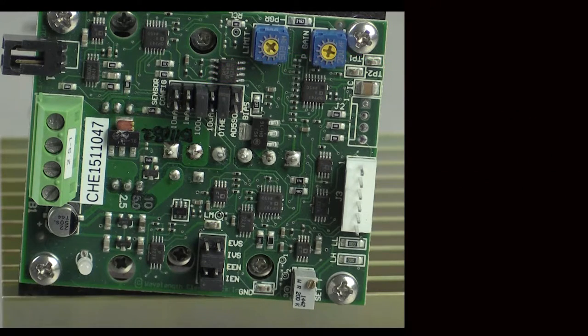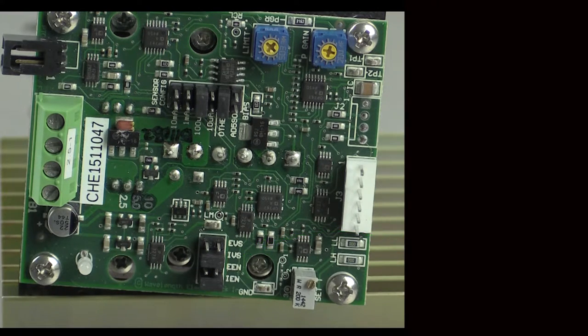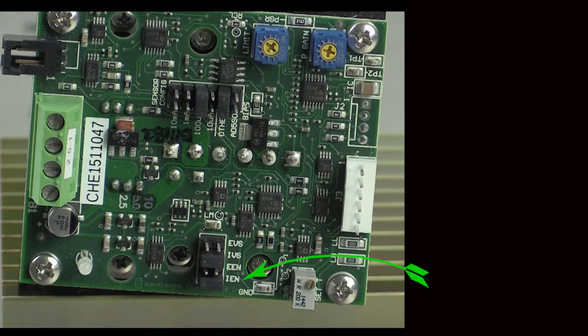We want to use the onboard setpoint trim pot, so make sure the setpoint jumper is on IVS, internal voltage setpoint. We'll also choose to have the output always enabled, so the enable jumper needs to be set to IEN, internal enable.